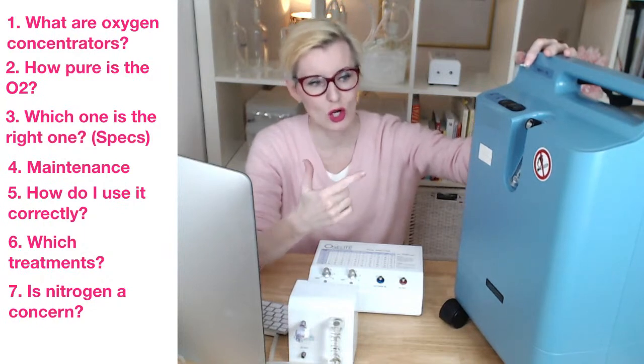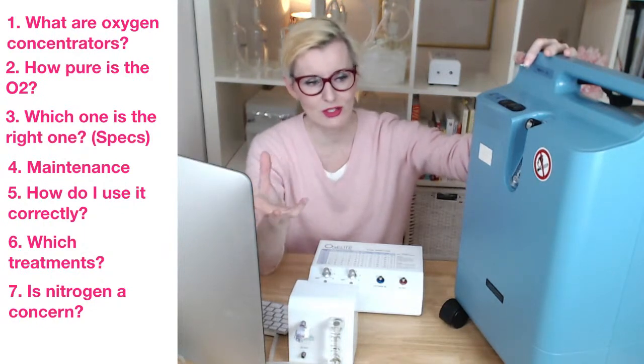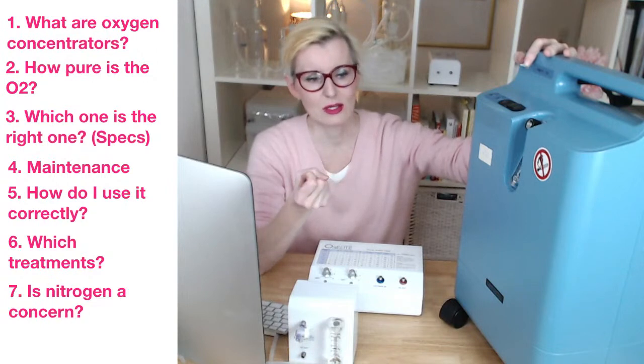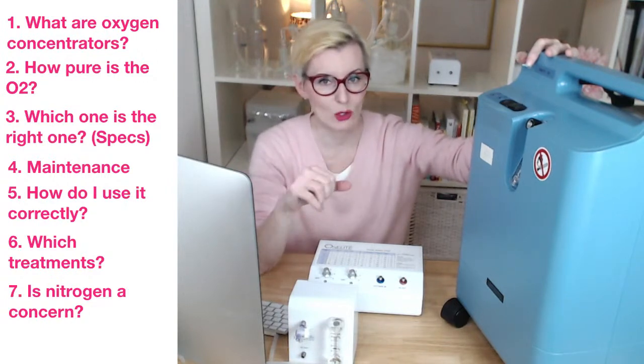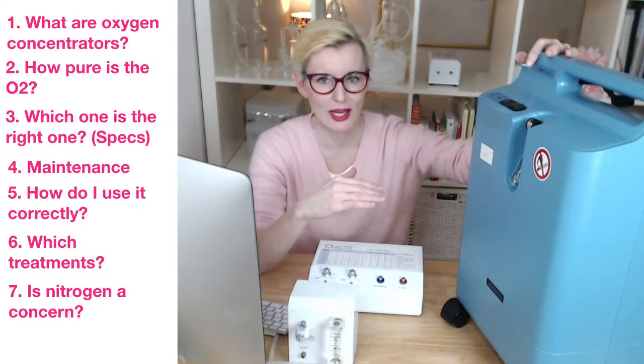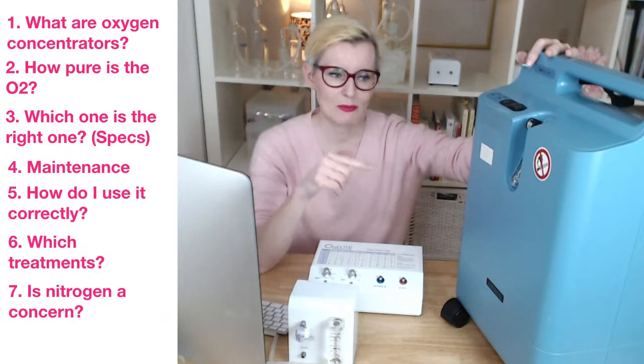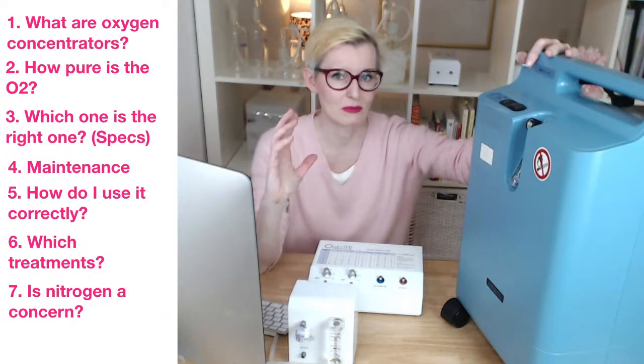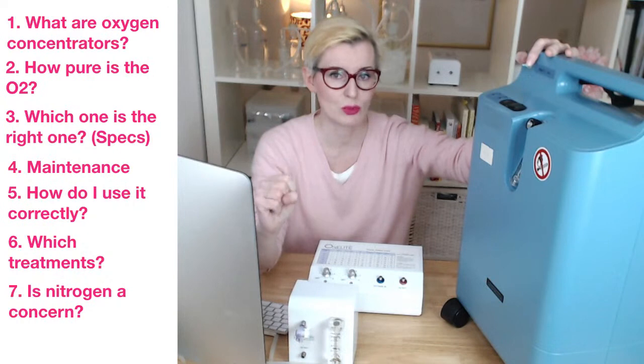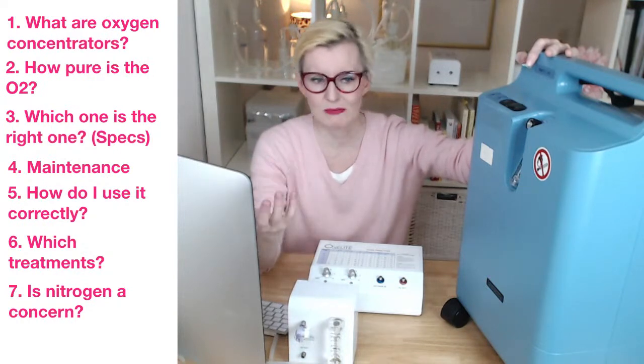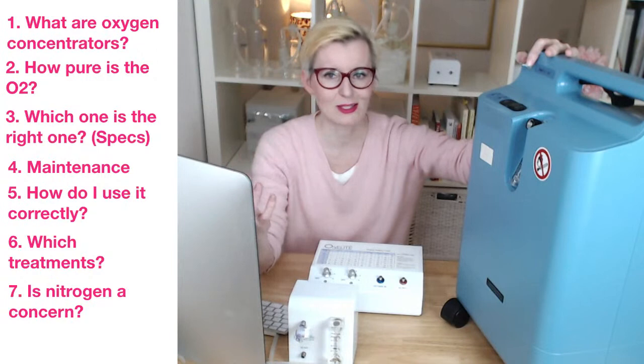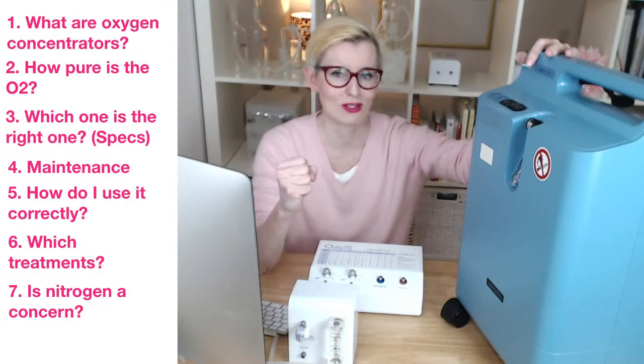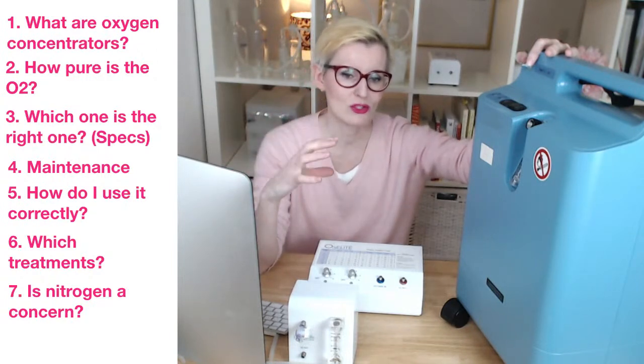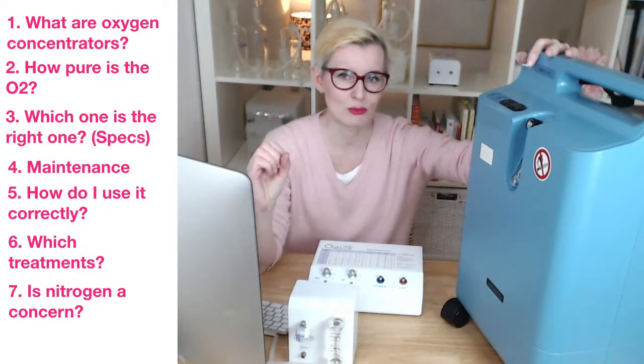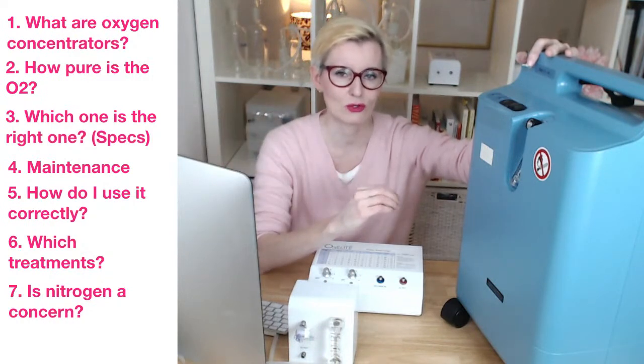And so what an oxygen concentrator does is it sucks in the air and filters the nitrogen out. It uses zeolite filters, and the zeolite binds the nitrogen. And so what comes out of the concentrator is 90 to 97% pure oxygen. So an oxygen concentrator does exactly what the name says. It concentrates the oxygen. It turns the gas that contains only 20% oxygen into a gas that contains up to 97% oxygen.